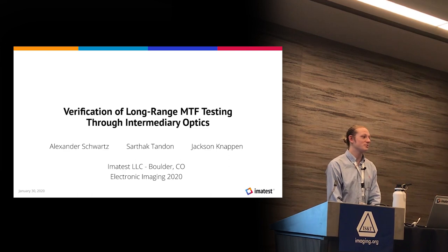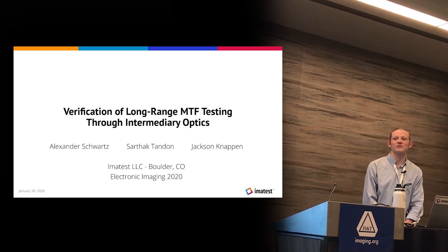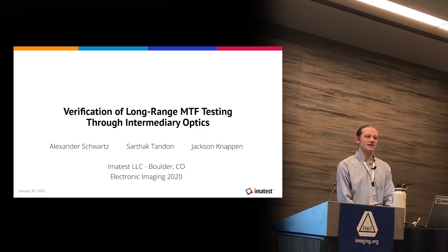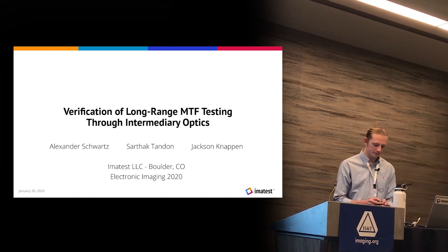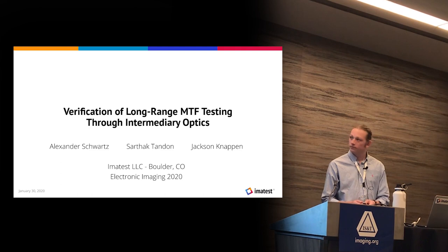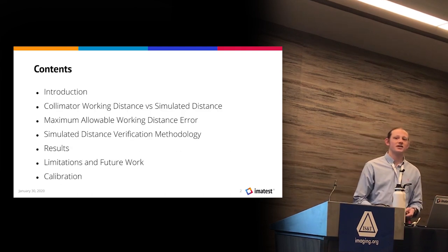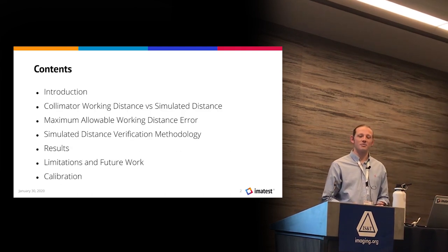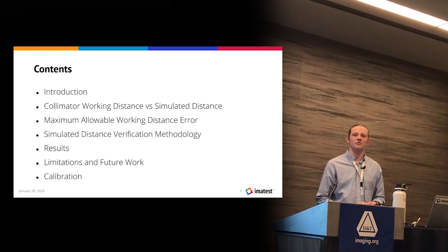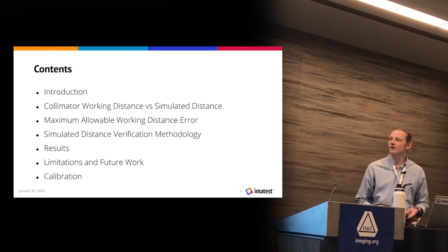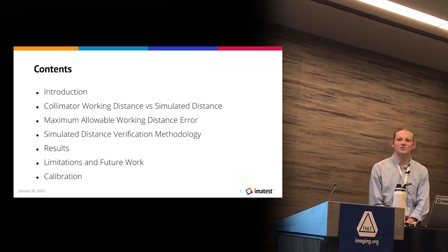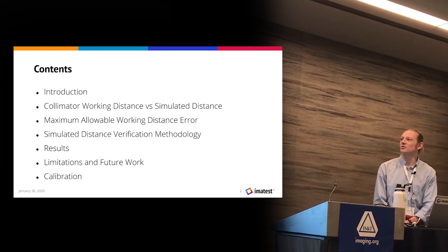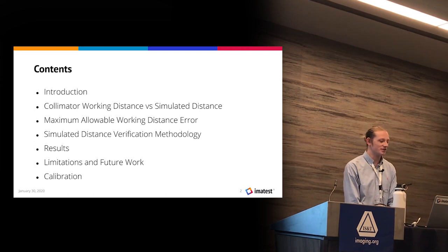I'm very excited to be presenting the method we've developed for validating simulated distances through intermediary optics. In this context, I'll be using the term intermediary optics interchangeably with relay lens or collimator. After introducing our collimator fixture system, I'll be discussing the relationship between working distance and simulated distance.